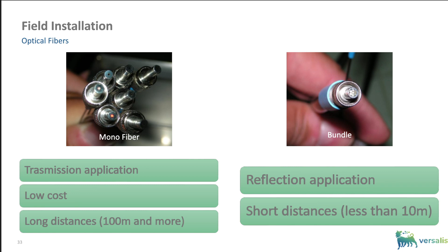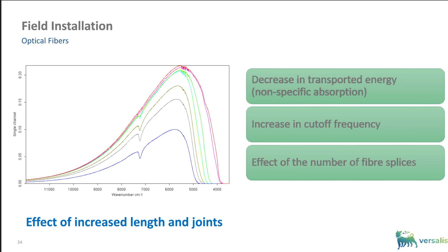But what is the effect of the length of the optical fiber on the collected signal? Basically, longer lengths result in a reduction of the collected signal, and also, which is not so obvious, a reduction of the spectrum amplitude. It has an increase of cutoff. It has the unusable spectrum. The blue one is a less intense signal, with amplitude less than the red one. The figure also shows how the long fiber can lead to irregularities in the spectrum, the small peaks, negative peaks.